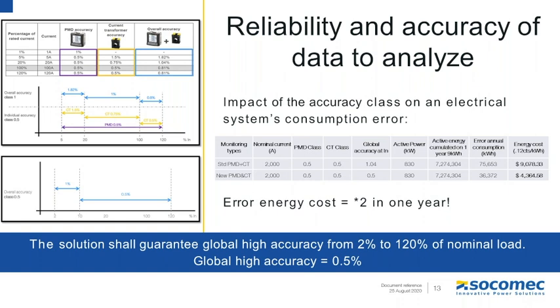Inside the example, we used the 2000 amp switchboard and we compared the two technologies result with error energy cost. So using the average cost per kilowatt hours in New England, which is 12 cents, you can see that there is a $5,000 cost difference between the basic power meter on top and the manufacturer guarantee global accuracy power meter at the bottom. So through this data, we can see that it's important to understand the global accuracy of the power monitoring device you're installing, because it's saving you money. And that's what Chicago Plastic was looking for, to save money.